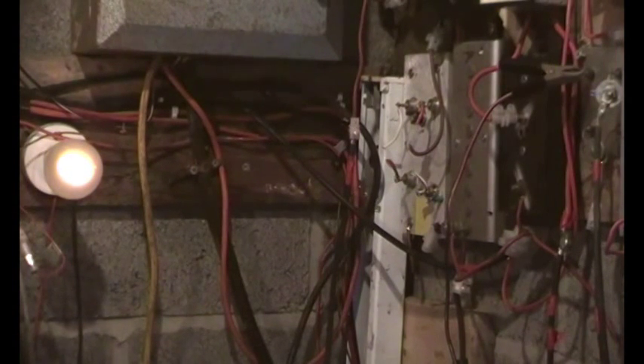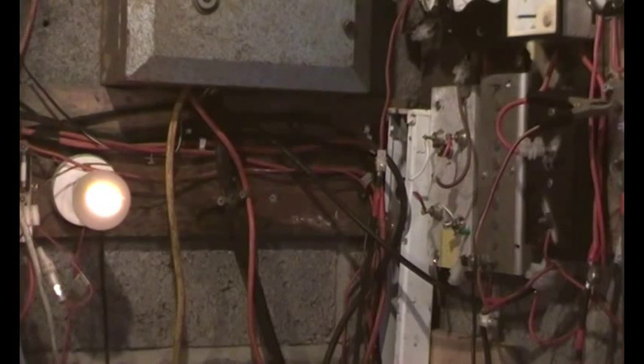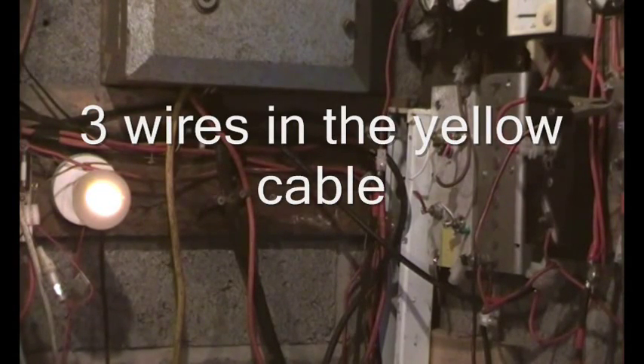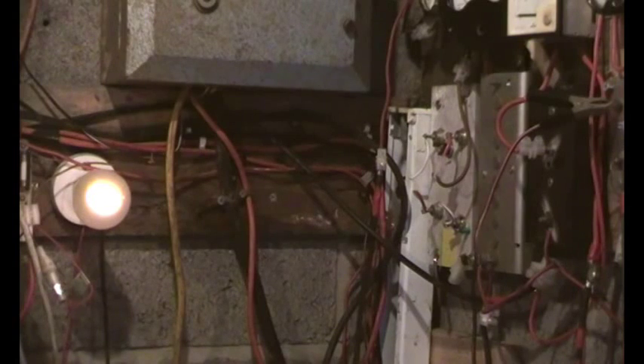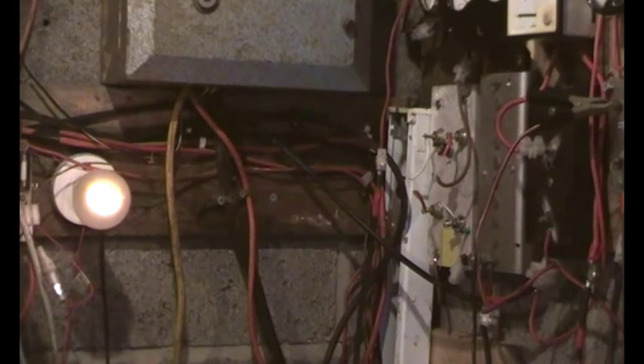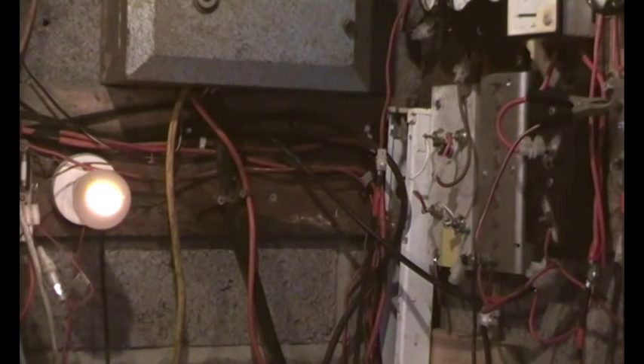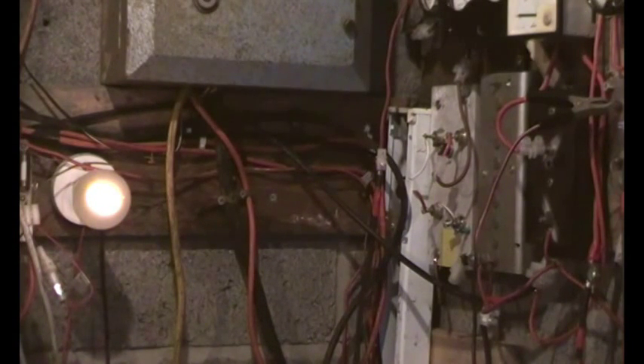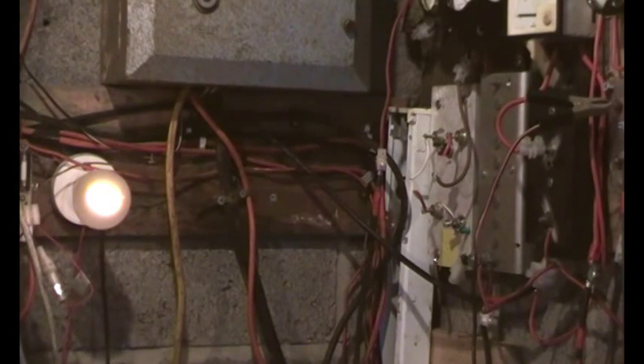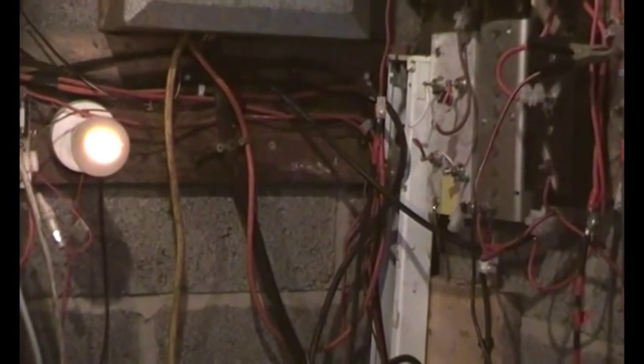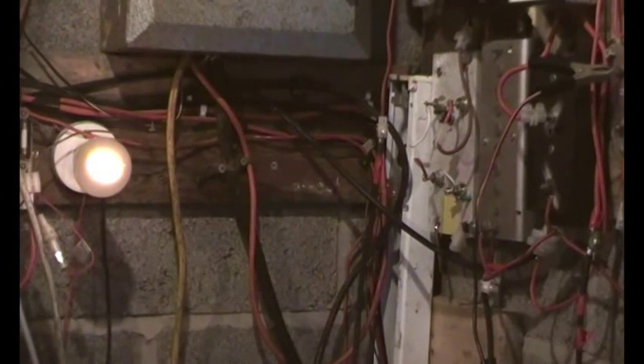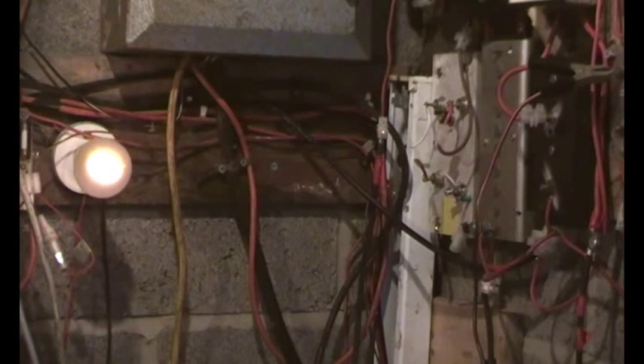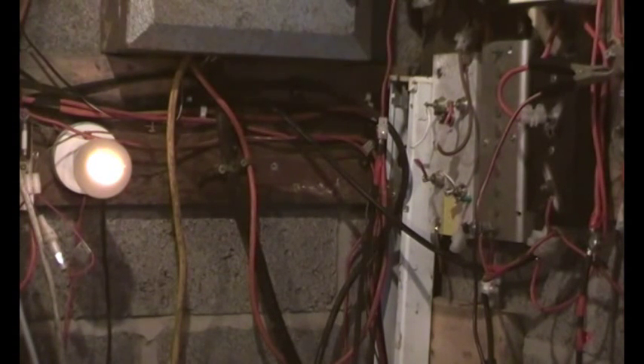What I'm going to do is remove that black wire and connect it to the end of this yellow. The brown and blue is the power to the tracking gate, so the blue is the common. I can attach the other wire in that three-core cable, which is probably green and yellow, and use that as a live against the common neutral. So we can get rid of that big ungainly black cable which is difficult to put in trunking.